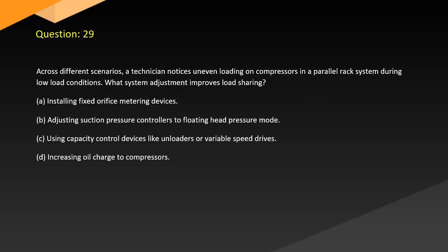Question 29. Across different scenarios, a technician notices uneven loading on compressors in a parallel rack system during low load conditions. What system adjustment improves load sharing? A. Installing fixed orifice metering devices. B. Adjusting suction pressure controllers to floating head pressure mode. C. Using capacity control devices like unloaders or variable speed drives. D. Increasing oil charge to compressors.